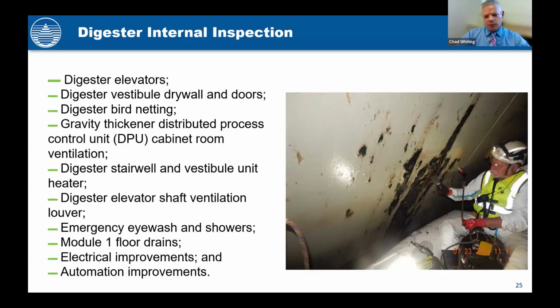We can't do all of them, so we're doing a select number to make sure we understand what the condition assessment is, so that we can properly project that into our design and make sure that we take care of everything during construction. Some of the lessons learned incorporated into the design report were we want larger overflow lines to prevent clogging. We want to have piping changes.